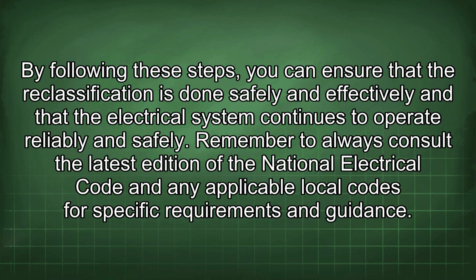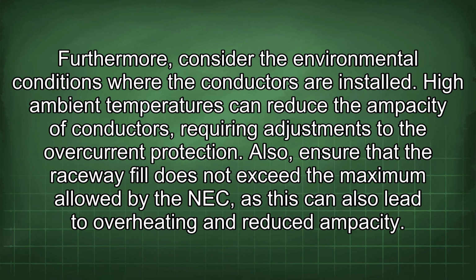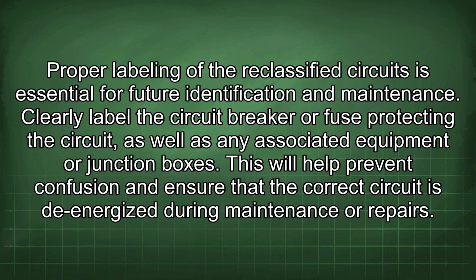Remember to always consult the latest edition of the National Electrical Code and any applicable local codes for specific requirements and guidance. Furthermore, consider the environmental conditions where the conductors are installed. High ambient temperatures can reduce the ampacity of conductors, requiring adjustments to the overcurrent protection. Also, ensure that the raceway fill does not exceed the maximum allowed by the NEC, as this can also lead to overheating and reduced ampacity. Proper labeling of the reclassified circuits is essential for future identification and maintenance. Clearly label the circuit breaker or fuse protecting the circuit, as well as any associated equipment or junction boxes. This will help prevent confusion and ensure that the correct circuit is de-energized during maintenance or repairs.